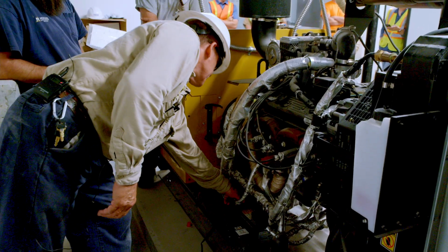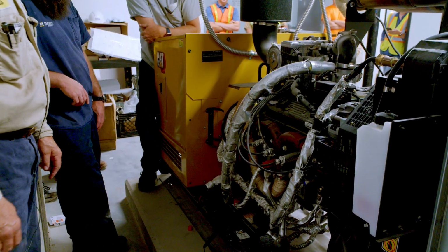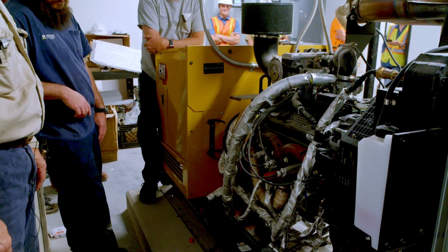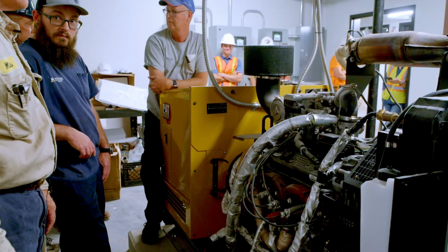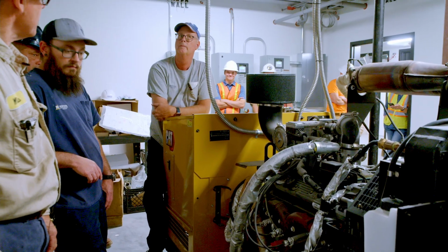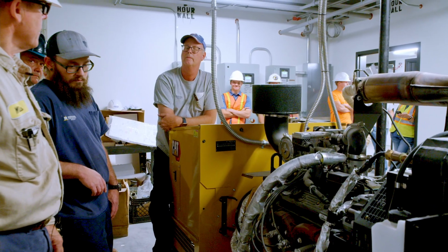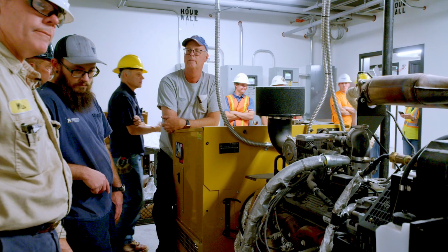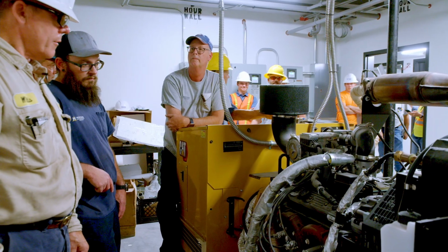It's got some flush caps. I recommend changing that every 3 years. Again, NFPA says 24 to 36 months, and that's typically what we do. That way you're about half-life on the battery.